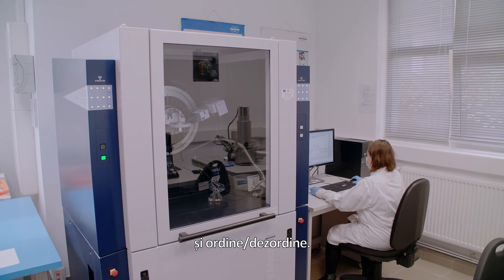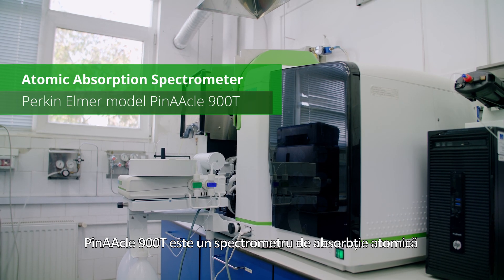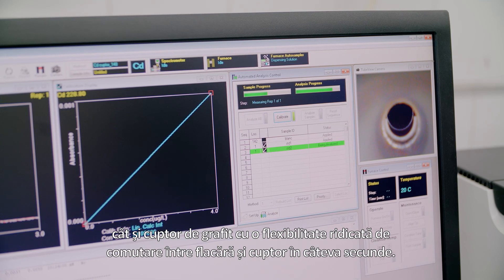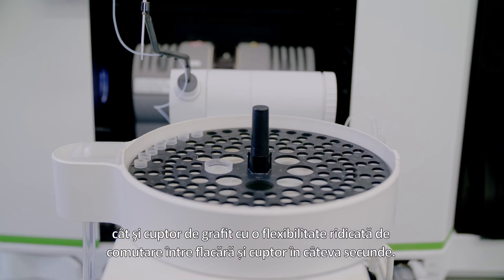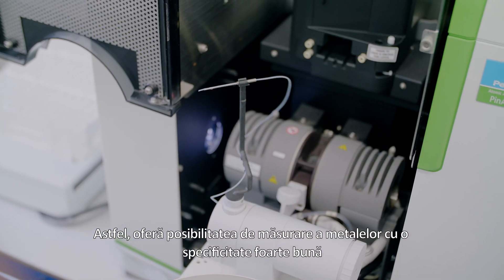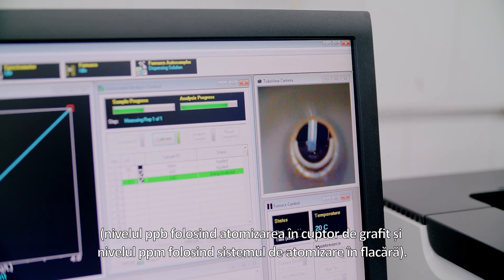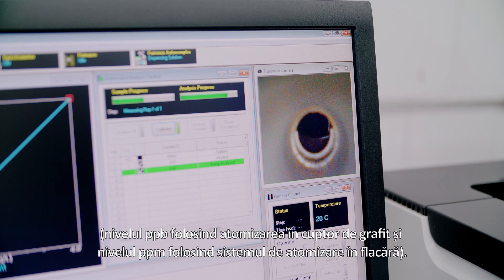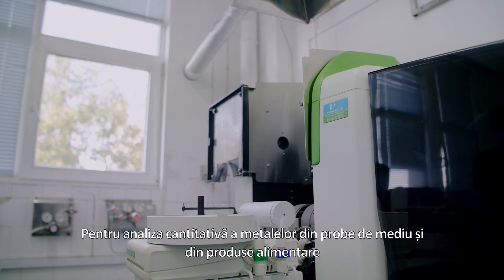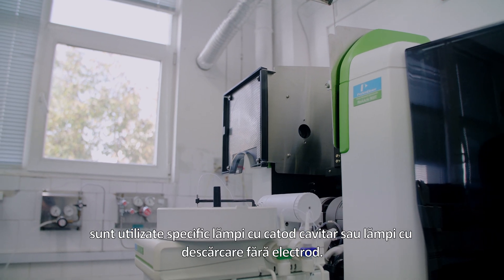The PinAAcle 900T is an atomic absorption spectrometer which includes in a single instrument flame and furnace atomization systems, with high flexibility to switch between flame and furnace in seconds. It provides capabilities for measuring metals with very good specificity over a wide range of concentrations — parts per billion level using furnace atomization and parts per million level using flame atomization. Hollow cathode lamps or electrodeless discharge lamps are used for quantitative analysis of metals in environmental and food samples.